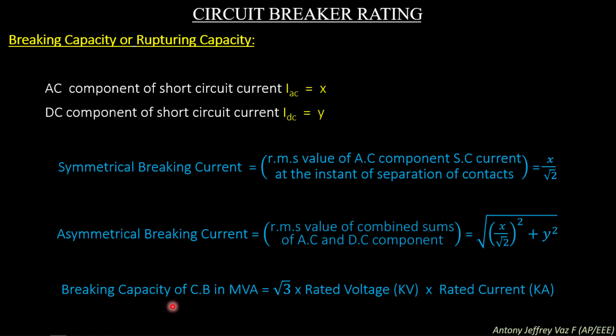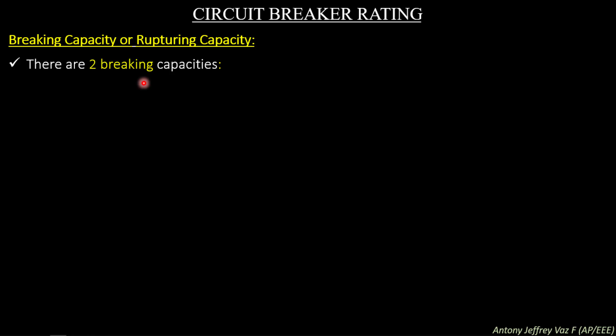The breaking capacity of a circuit breaker is expressed in MVA, which is root 3 times rated voltage in kV times rated current in kA. Both values are in kilo: kilovolt into kiloampere into root 3 for 3 phases. We give the breaking capacity of the circuit breaker as an MVA rating. There are two breaking capacities: one is symmetrical breaking capacity and the other is asymmetrical breaking capacity. The symmetrical breaking capacity applies when only the AC wave is present, and the asymmetrical breaking capacity applies when there is the AC wave and also the DC component.